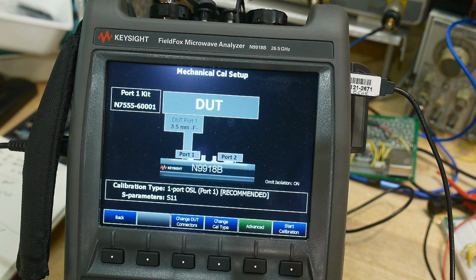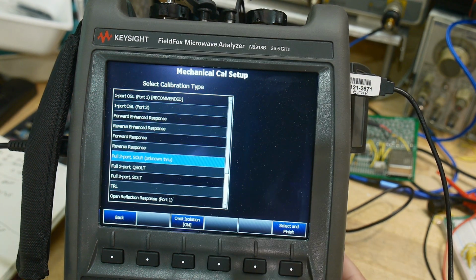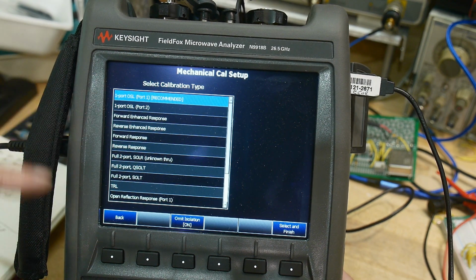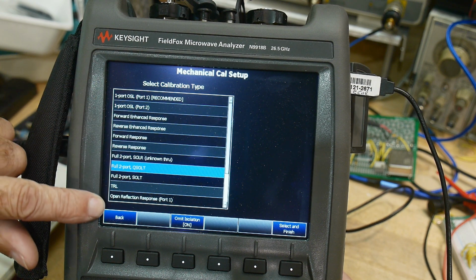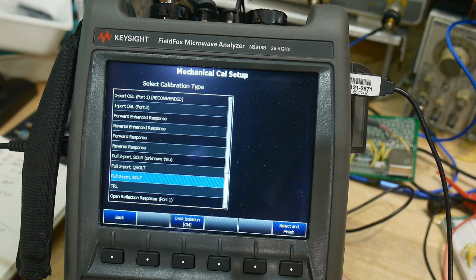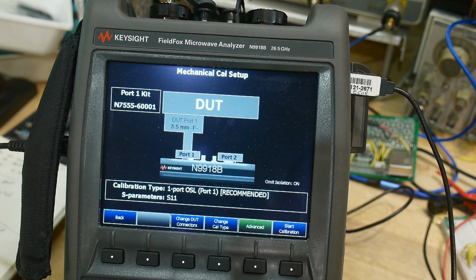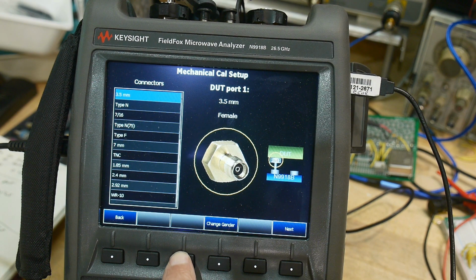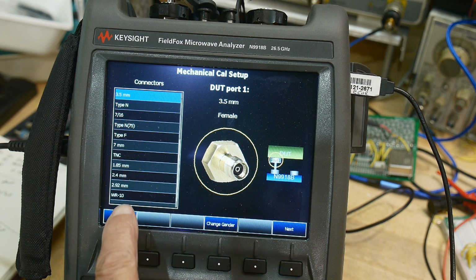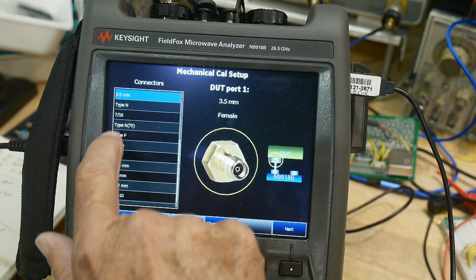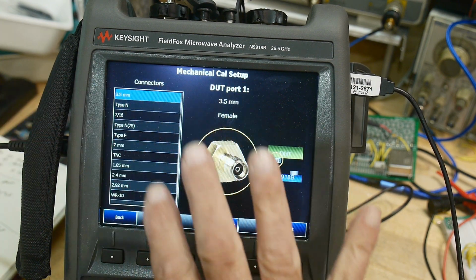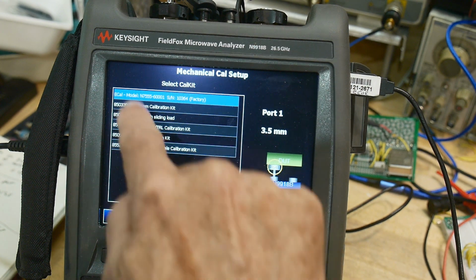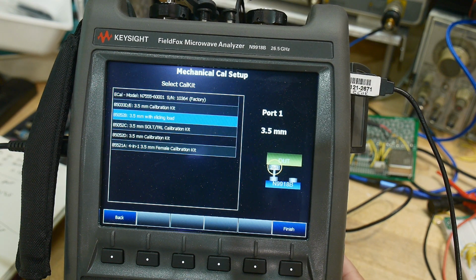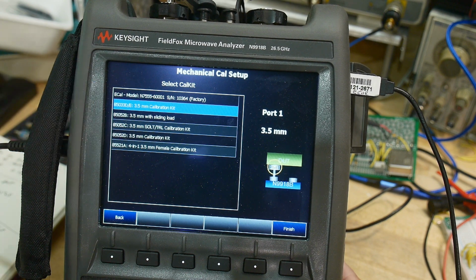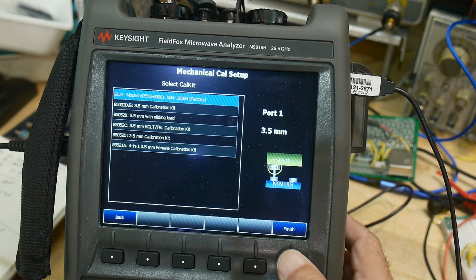Okay, and the way that you get here is to hit the button change cal type. This is something else. I'm sorry, but you can do a 1-port, or you can do a 2-port. You can do a short open load through. So you can do all kinds of stuff. Okay, we're just going to do an open short load, let's see, change connectors. Yeah, this is how you get to the eCAL. You say change connectors, and it says, okay, what connector you plug into this thing, and it says all of these choices. Well, we have a 3.5 millimeter connector, so that's fine. And we will hit next, and then it comes up with, well, which calibration kit do you have? And normally it defaults to something like the first one or something, but this one at the top here says eCAL.